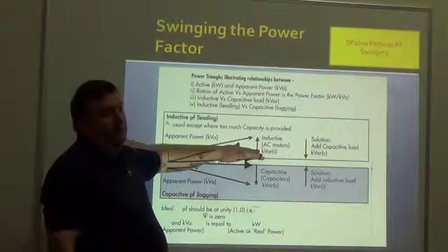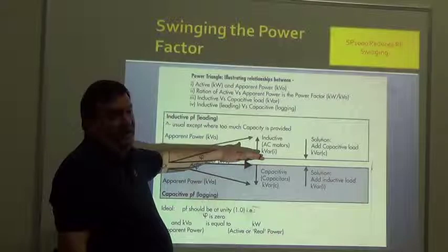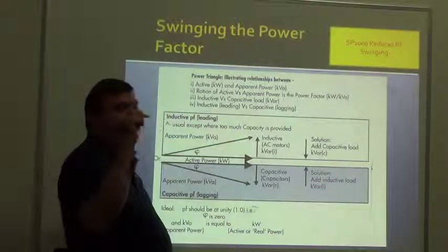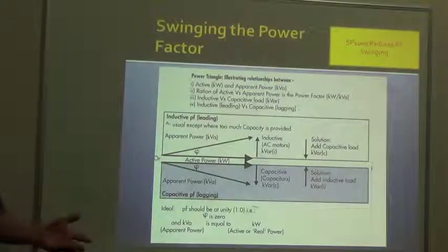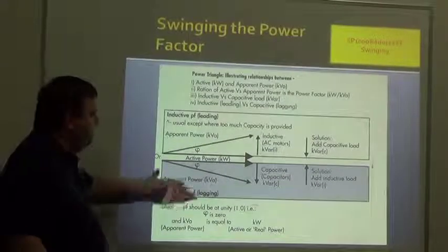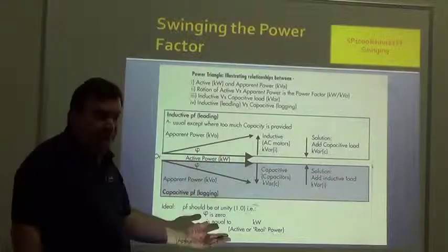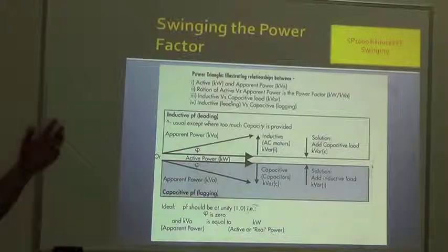And we're at the mercy of the utility, because the utility might not feed us voltage that's clean. It might look very nasty for a few hours. And that's gonna make the harmonics worse, because we're feeding harmonics into a system that already has harmonics to begin with. So there's never been a good way to manage this according to the load and the conditions of the power, inside and outside the building.